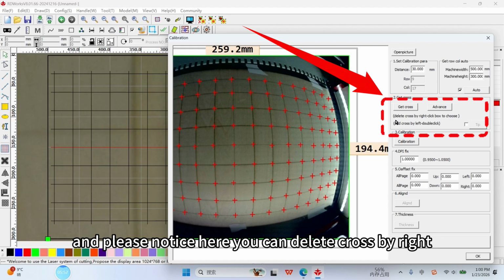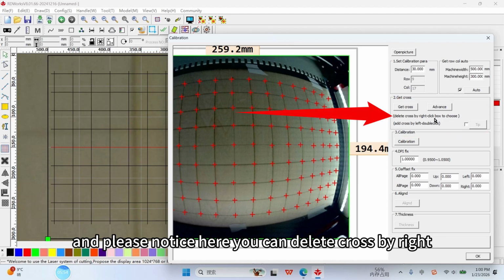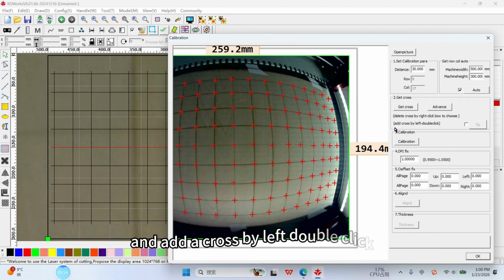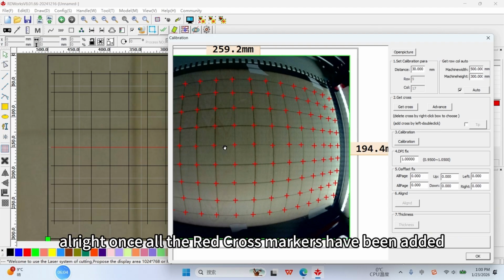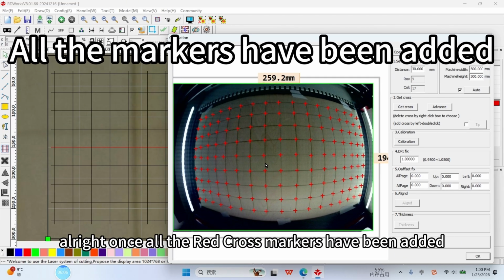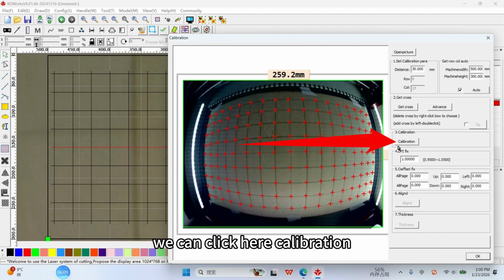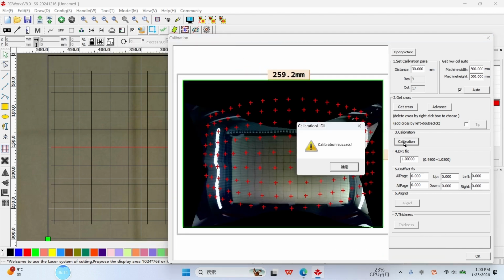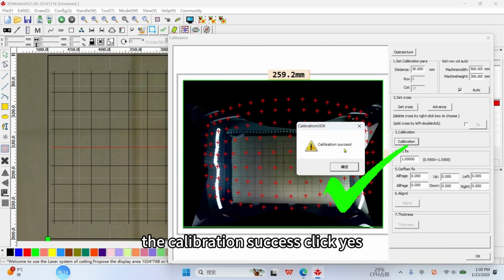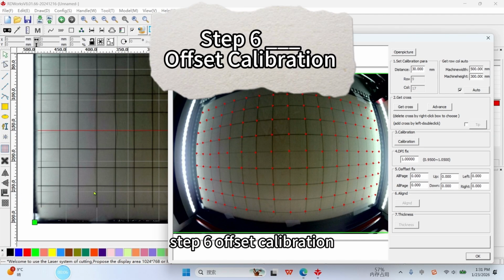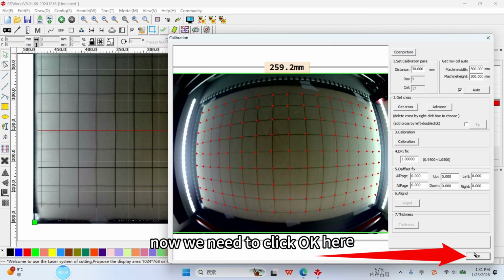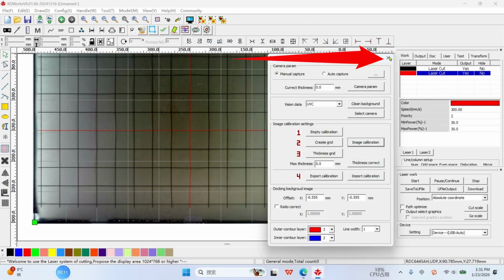And please notice here, you can delete a cross by right-clicking the box to choose it, and add a cross by left double-clicking. Alright, once all the red cross markers have been added, we can click here, Calibration. The calibration is successful. Click Yes. Step 6, Offset Calibration. Now we need to click OK here.